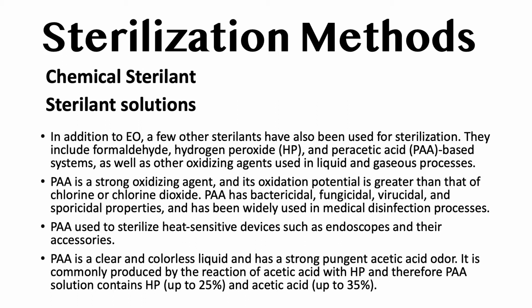Sterilant solution. In addition to ethylene oxide, a few other sterilants have also been used for sterilization. They include formaldehyde, hydrogen peroxide, and peracetic acid based systems, as well as other oxidizing agents used in liquid and gaseous processes. Peracetic acid is a strong oxidizing agent, and its oxidation potential is greater than that of chlorine or chlorine dioxide. Peracetic acid has bactericidal, fungicidal, virucidal, and sporicidal properties and has been widely used in medical disinfection processes. Peracetic acid is used to sterilize heat-sensitive devices such as endoscopes and their accessories.